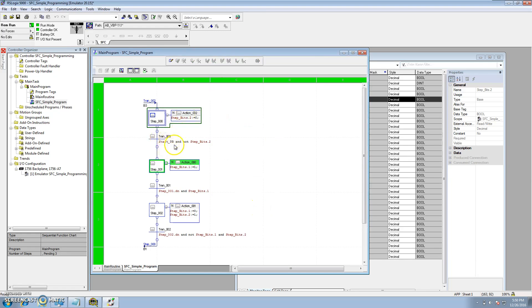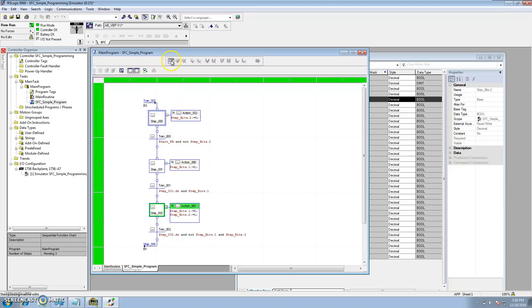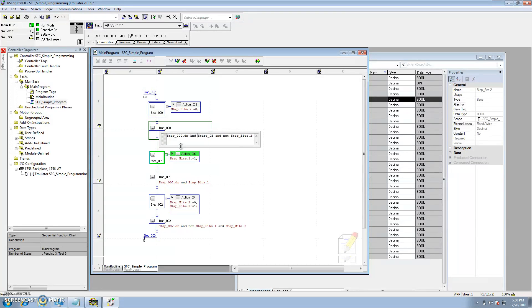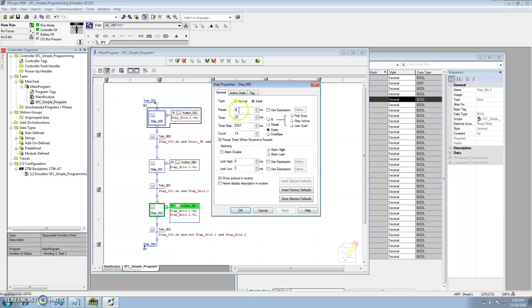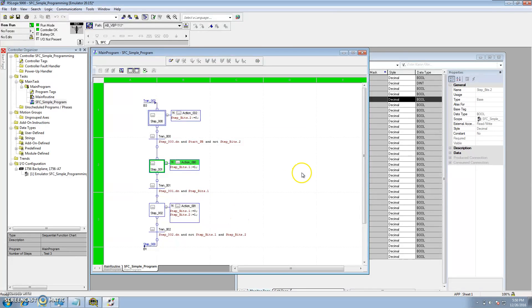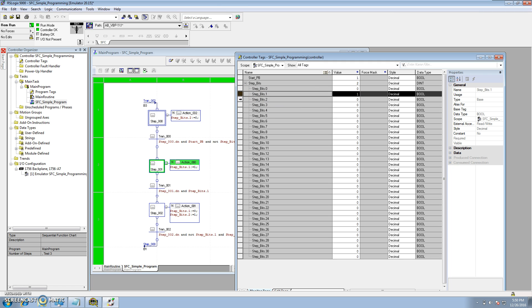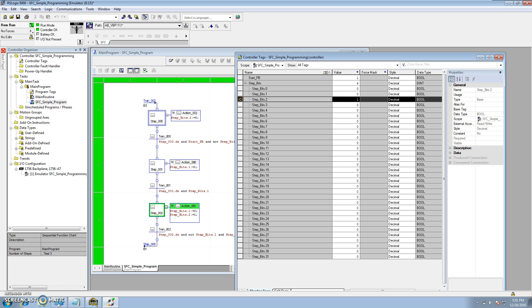We don't have a timer for step 0 right here, so we can stop it real quick and add step 000 done. We can throw in a timer there and finalize. Now we can see the whole transition: it goes to zero, then cuts on step_bits.1, then step_bits.2 is on, and then when it goes back to step 0 it cuts everything off.